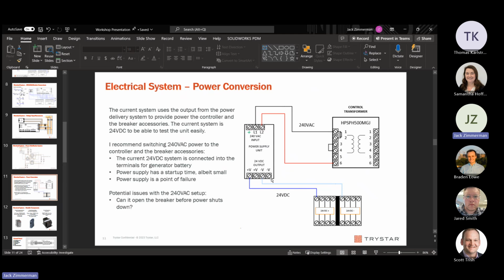Because what would happen is your controller power comes back, and then it tries to do something to the breakers, and the 24 volt DC power supply that actuates those accessories is not up yet to be able to, so it would have to reissue the command after 10 seconds or whatever you set it to. So that's not ideal, because the power supply is pretty fast. It's 350 milliseconds, but this controller will send a signal within 10 milliseconds if it wants to. So it's just too fast for doing that.